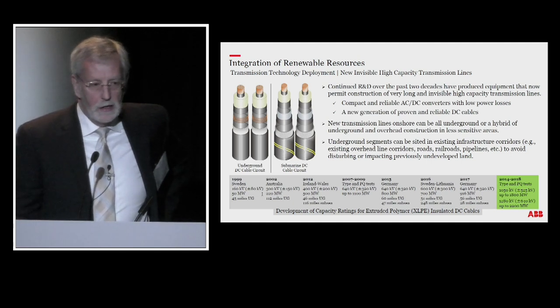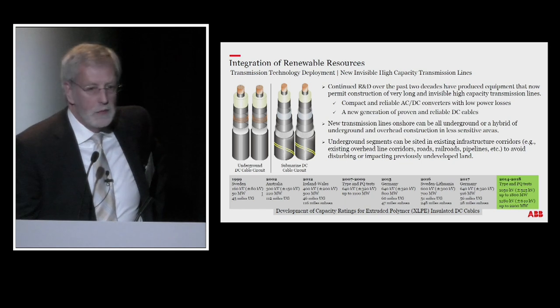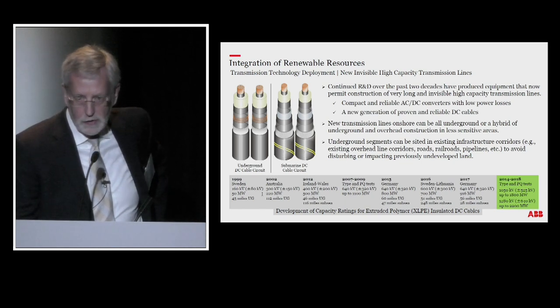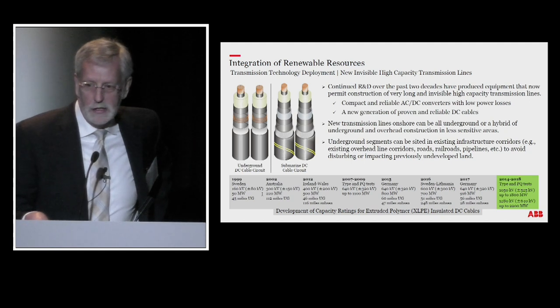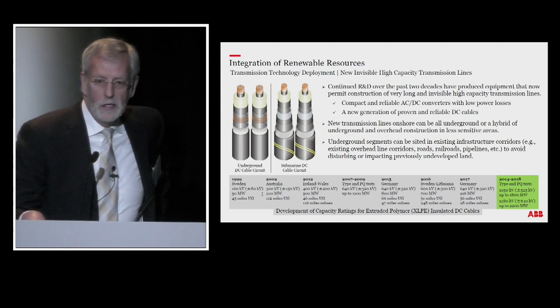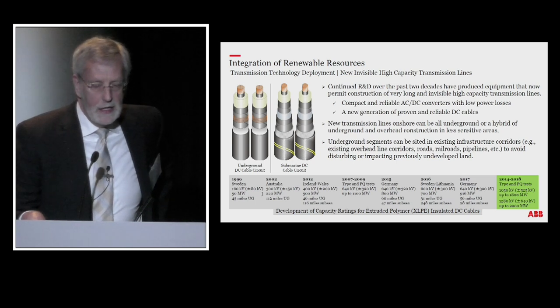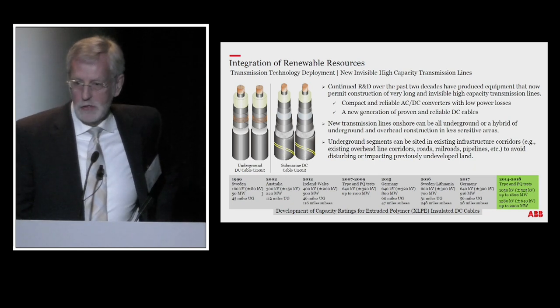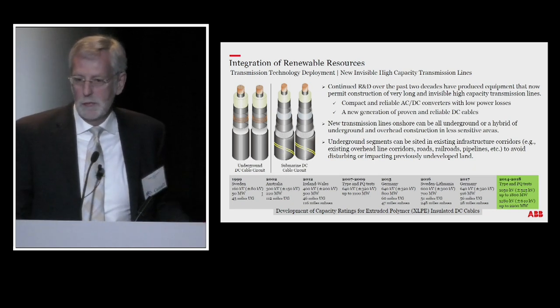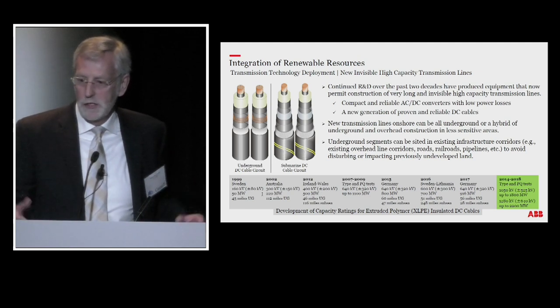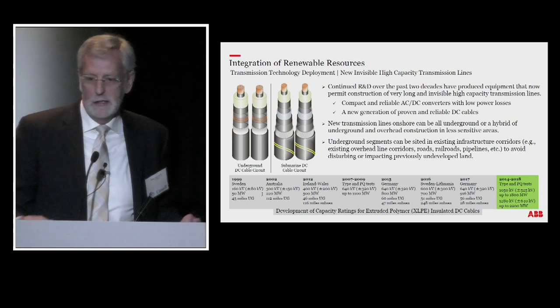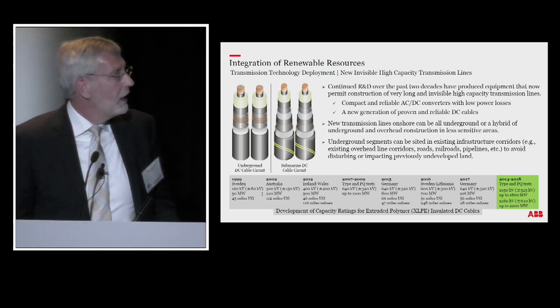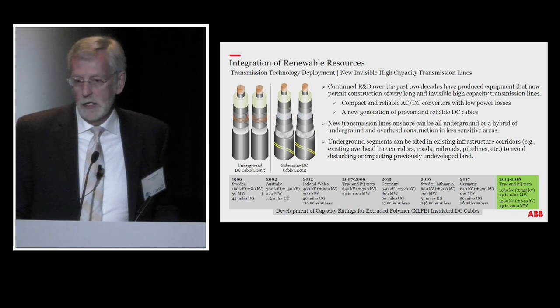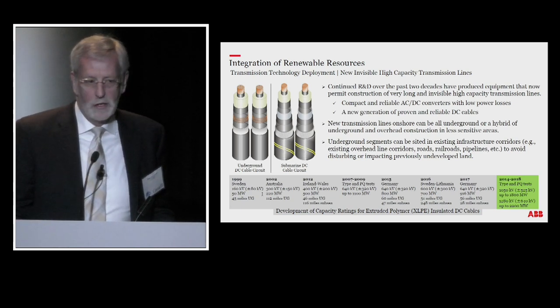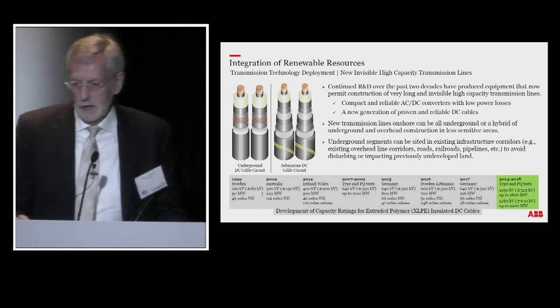You can do it along roadways, and you may ask, why don't you do this with AC? Well, with AC there are some technical issues. When you operate underground or submarine cable with power frequency, you create very high charging currents that essentially use up the transmission capacity of the cable once you get to a certain length. But if you use DC technology, all of those issues go away, and there is really no technical limit on how far you can go underground or underwater—it's just an economical issue.